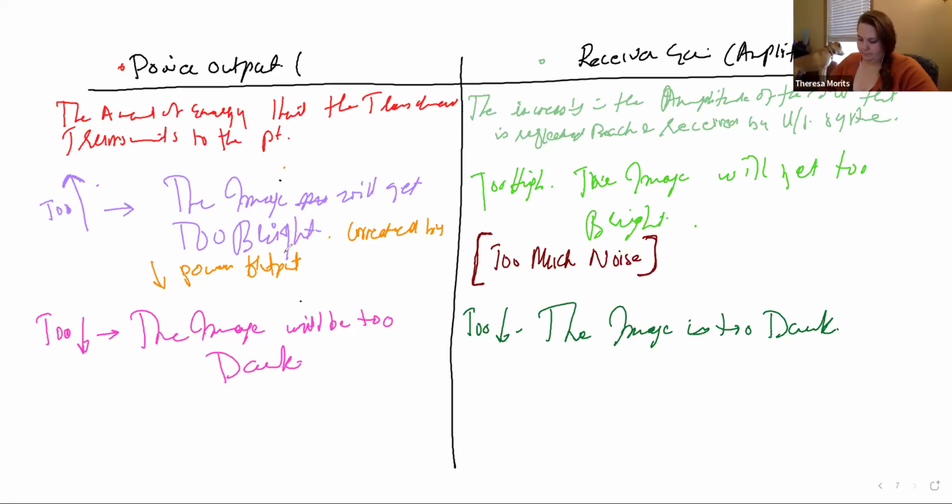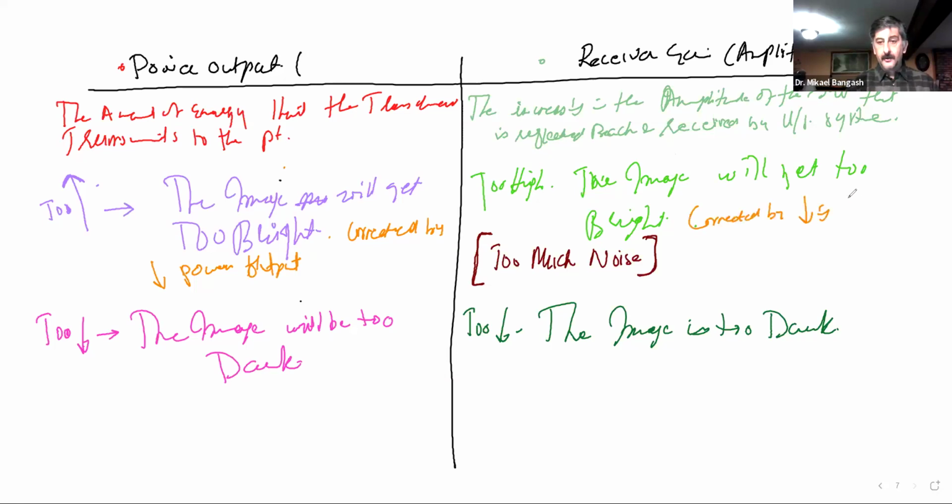Good. Or likewise, if your image was too bright, it could be corrected by reducing the receiver gain.